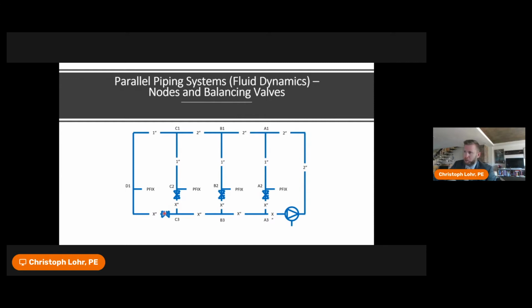Now, a lot of people say, well, assuming this is to scale, you don't need that D loop balancing valve. And that is technically correct. However, I typically see many engineers add this just in order to make sure they have more controllability of the system. That is, if there's another loop that gets added at a later date, they have a valve in there already rather than having to add it at a later point.